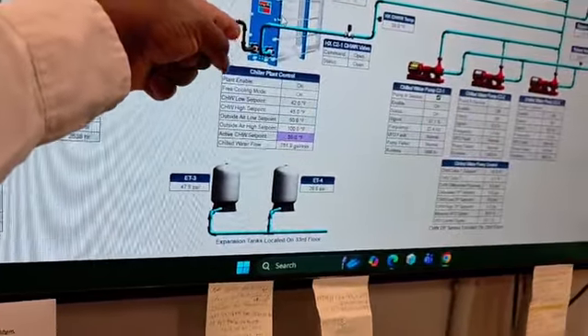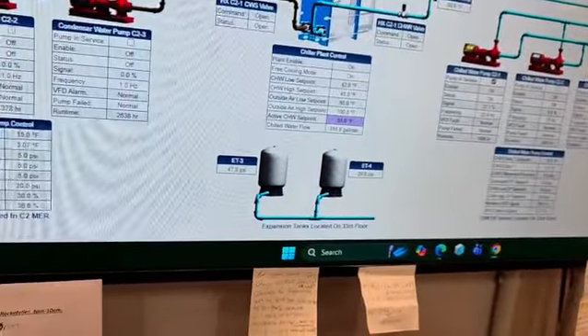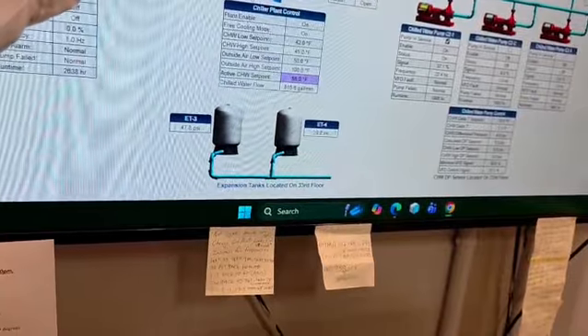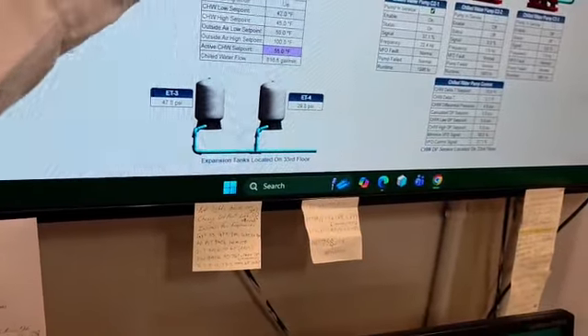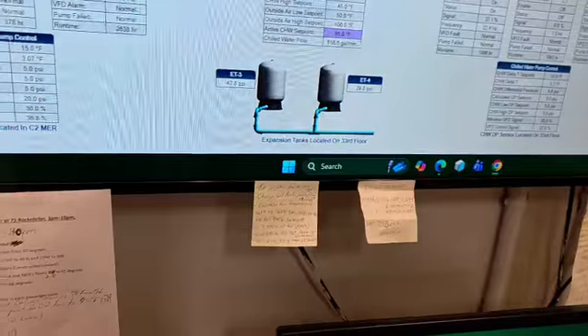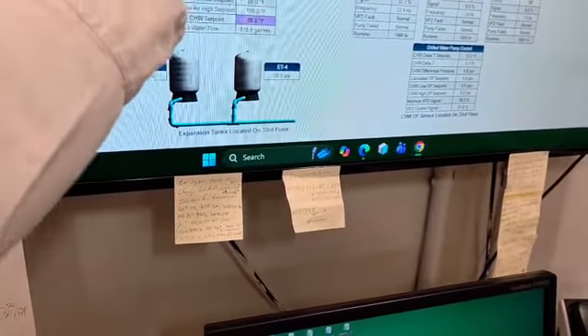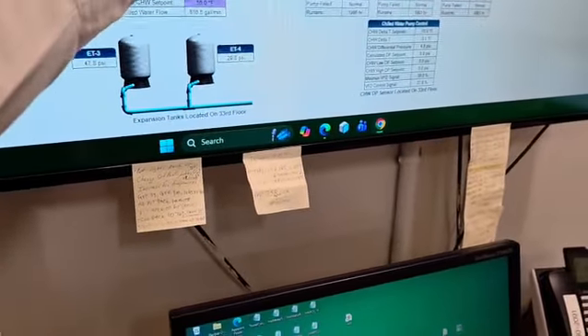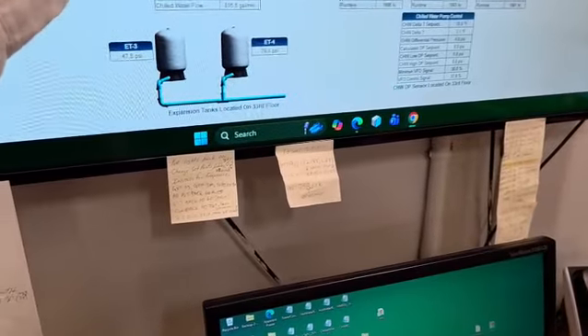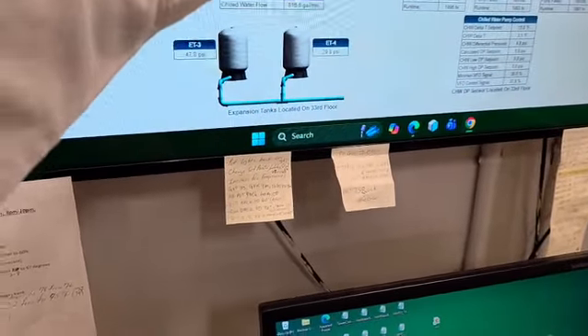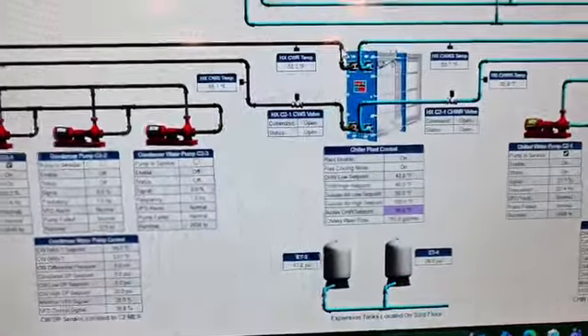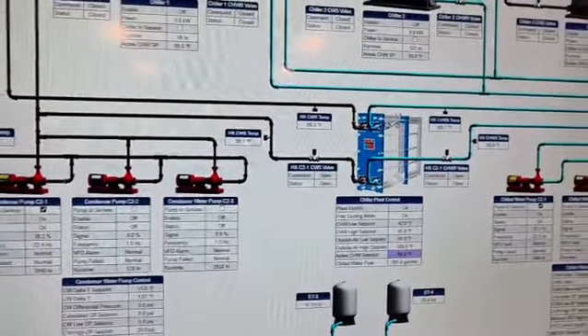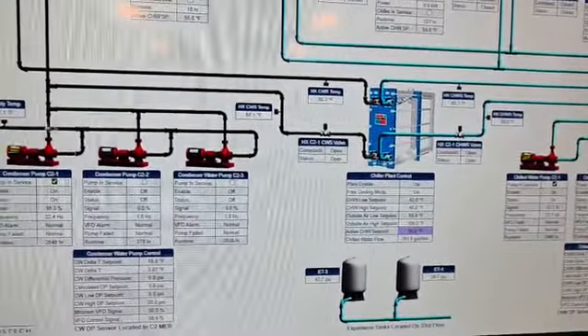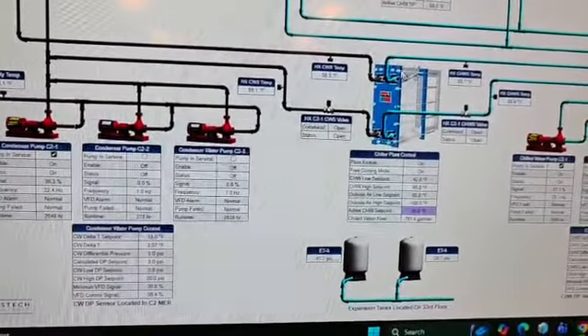This is coming in. Let's say the temperature is lower here, this is coming in colder, right? And this one went already through the building, so it's coming in hotter. So the heat moves from this side to this side. No, the other way around. From this side, from the blue into the brown. Oh yeah, that's right. It moved from the blue into the brown. The brown goes up to the cooling tower, cools again, and comes back down. And again the same cycle, right?